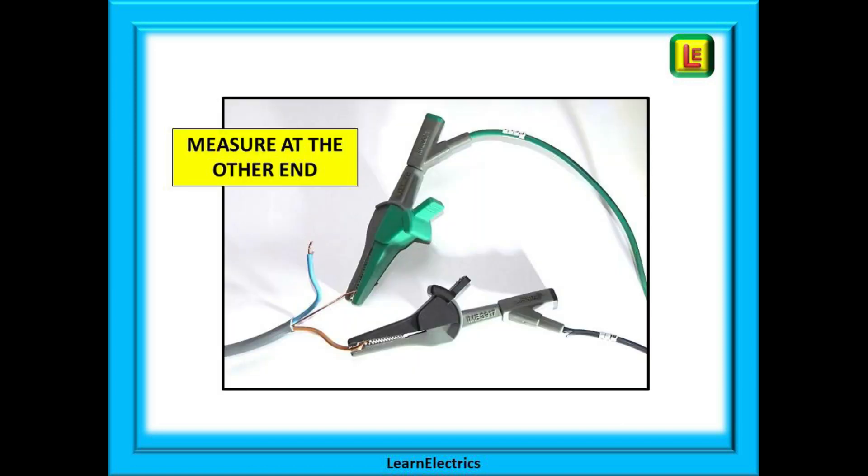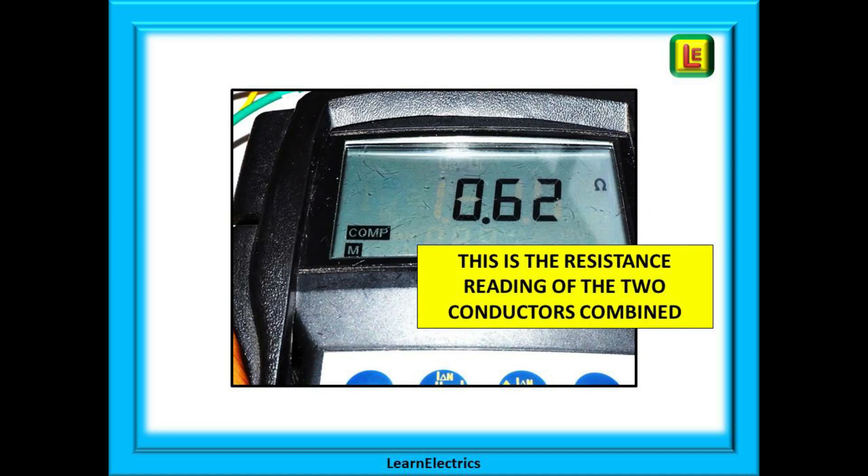At the other end of the cable we keep the conductors separate. Again strip back the brown, connect one lead of your meter to it and the other lead to the earth as shown. With the meter set on low ohms measure the resistance and I recommend you write it down. In our example the cable measures 0.62 ohms. That is the resistance of the brown conductor and the earth conductor combined. We have measured all the way down the brown wire through the connection and back up the earth wire.